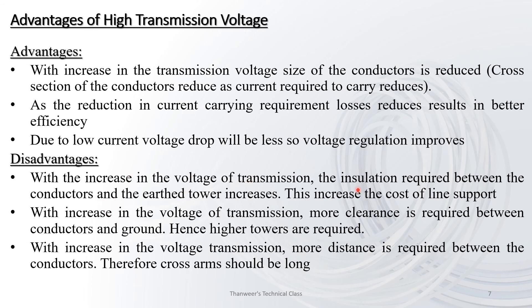Disadvantage: with the increase in transmission voltage, the insulation required between the conductors and the earth towers increases. Higher voltage requires greater insulation, increasing the cost of line support. With increase in voltage, more clearance is required between conductors and the ground, so higher towers are required. Cross arms should be longer as more distance is required between conductors.